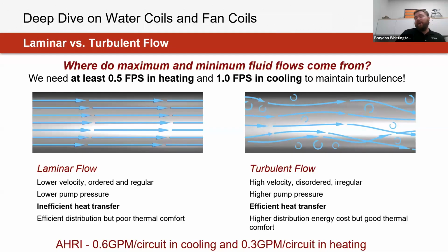Well, actually, and surprisingly, and this ties back to heat transfer, for those that haven't answered, the more predictable performance is actually going to be turbulent flow. Turbulent flow is more disordered in how the water flows through the coil, but in terms of predictability, that's where the most efficient heat transfer is actually occurring within the coil itself. So when you're rating performance or generating performance through software, what we're actually going to see are minimums or maximums for those coils through those tools. And those minimums are typically based off of the range in which it transfers, or is predicted to transfer, between turbulent and laminar flow.